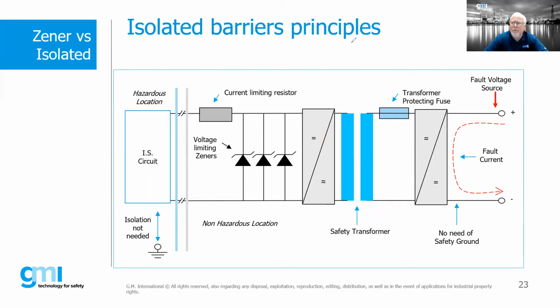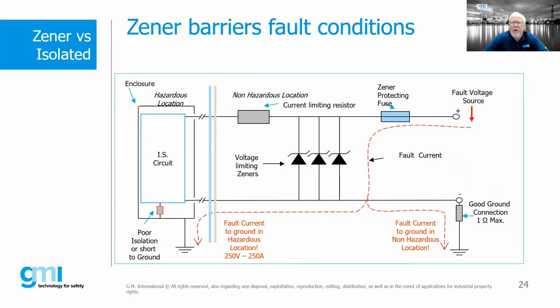So that's an important point to remember. Under a fault condition, I already mentioned this a little bit, but if we had a situation where we potentially could have that fault current go to ground in the hazardous area, if we don't have a good ground in our IS circuit at the point located within the hazardous area, and certainly if we don't have a good ground connection outside of the hazardous area, this is the big problem, if you will, for Zener diode barriers.